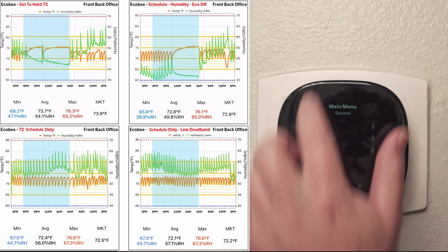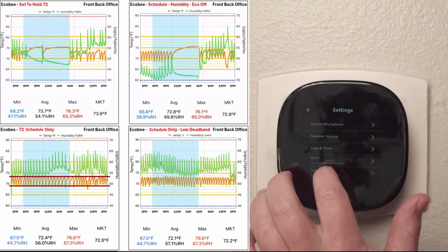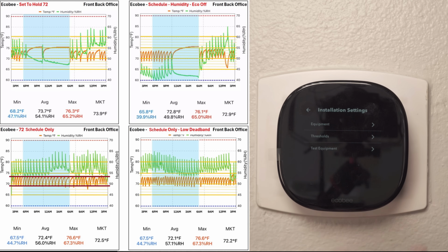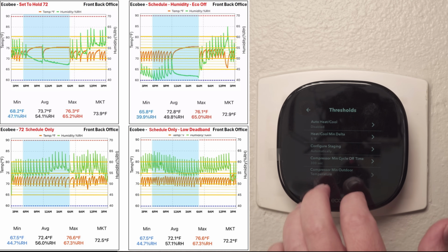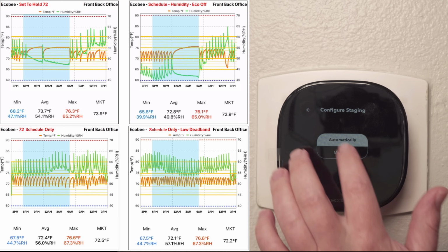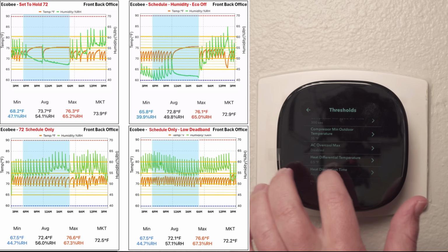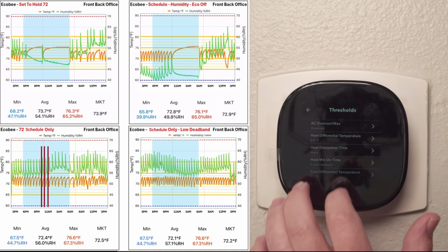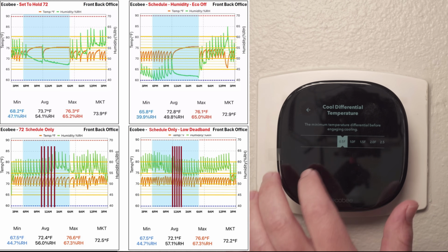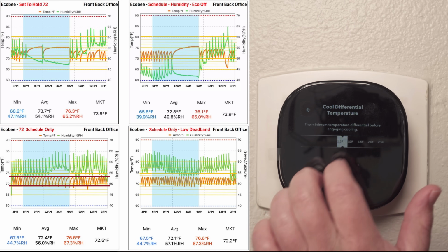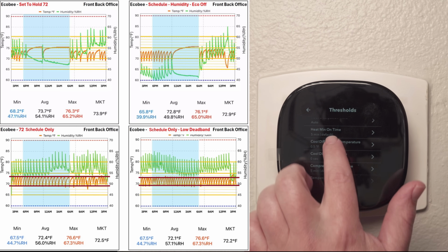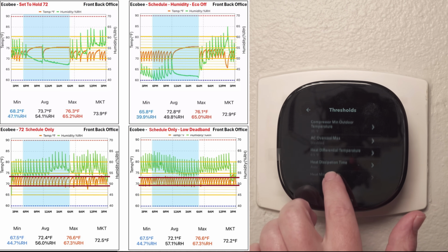From there, I wanted to lower the on-off temperature swings to give a more consistent temperature, kind of like the Honeywell thermostat, which helps with hot and cold spots. So I lowered the temperature cool difference to 0.5 degrees to get the system to cycle more often. It did cycle a bit more, and the temperature delta dropped by about a degree, but overall not as dramatic as I was hoping for.